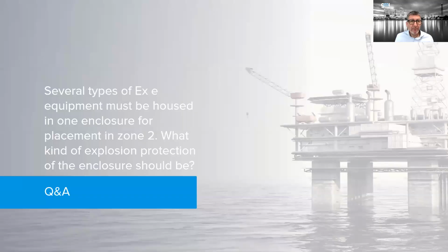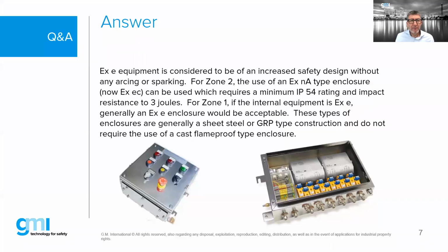So next question. Several types of Ex e equipment must be housed in one enclosure for placement in Zone 2. What kind of explosion protection on the enclosure should be used? Now, okay, we have a similar question, but this is a little different. On Ex e equipment, it's considered to be increased safety, where an enclosure is generally a sheet metal box. So if we had an explosion on the inside of a sheet metal box, it wouldn't contain it, right? So the equipment that we put inside must be Ex certified in and of itself.